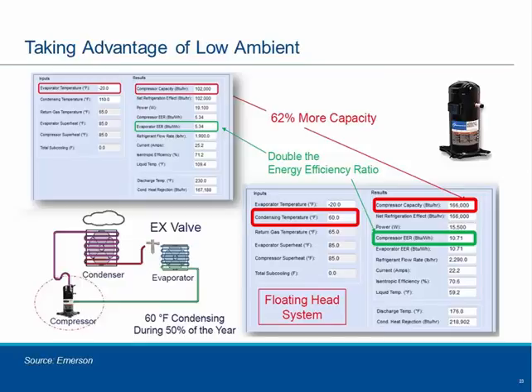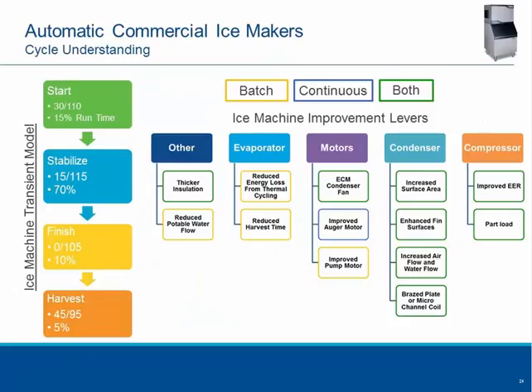And in this example, this calculation for this compressor, when you take advantage of that lower condensing, you not only get a lot more capacity, 62% more capacity out of the refrigeration system, but because the refrigeration system is not working as hard to move the heat, you're actually doubling the energy efficiency ratio or the EER of the compressor. And you can download that tool for free and try that out for yourself and see what kind of savings can be had just by floating the head pressure. So to learn more about that, check with E360.